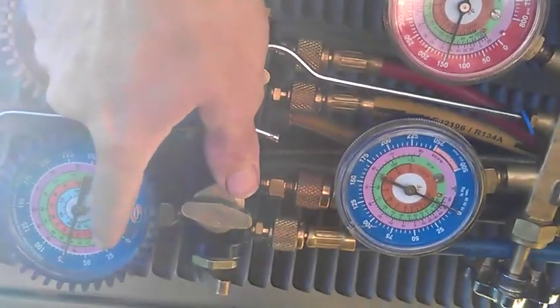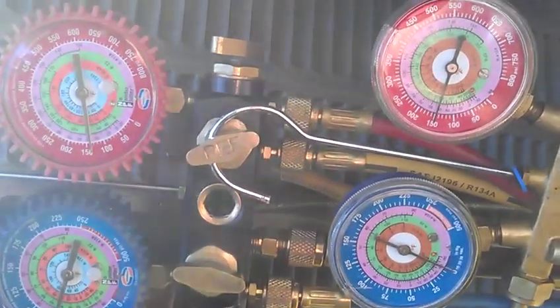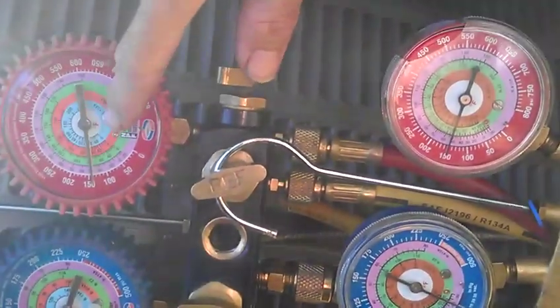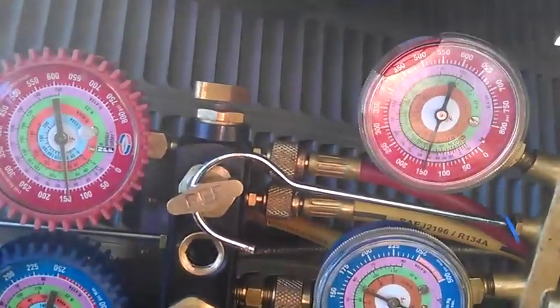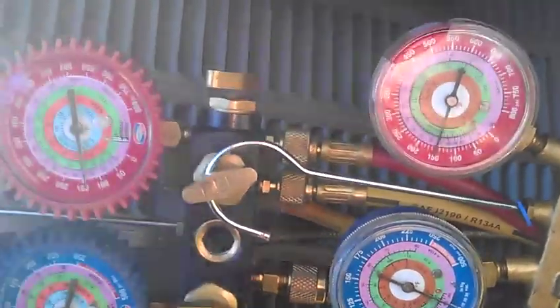Now if this gauge fell into a vacuum and these two stayed about the same, outdoor TXV will have failed. If this one stays good, this one stays good, but this one pulls into a vacuum and then your suction pulls into a vacuum, that's a liquid line restriction or indoor TXV failure in heat mode, and that's what ends up happening.